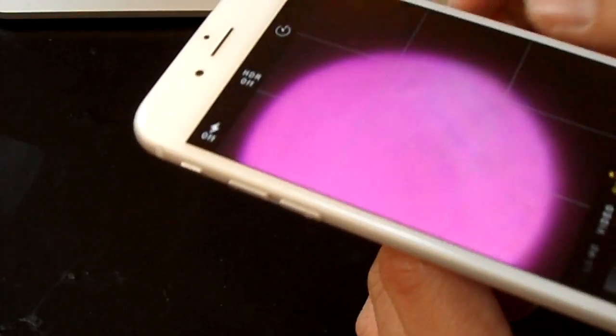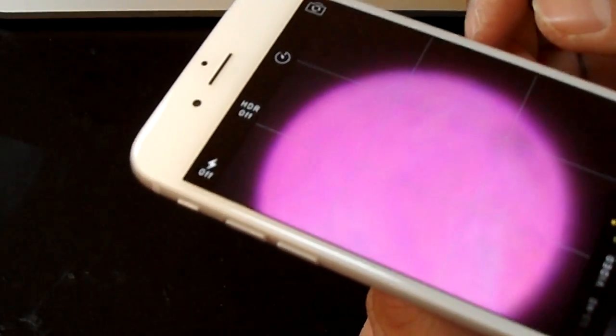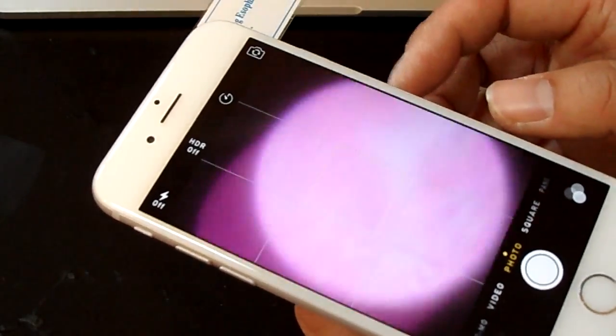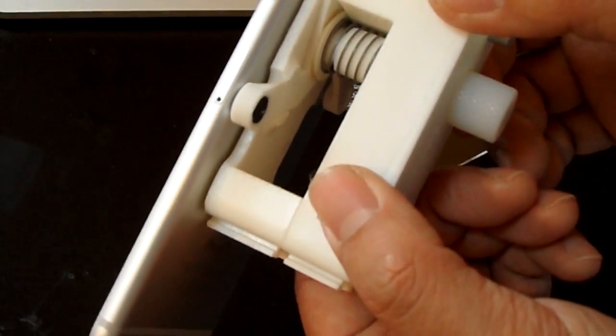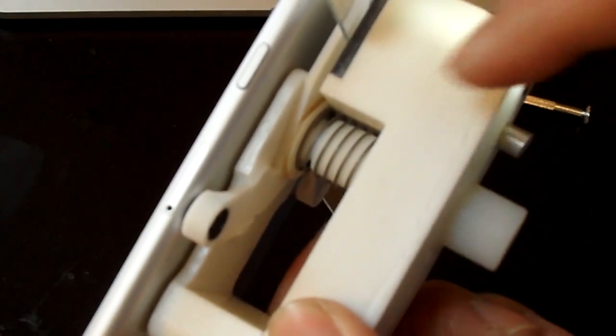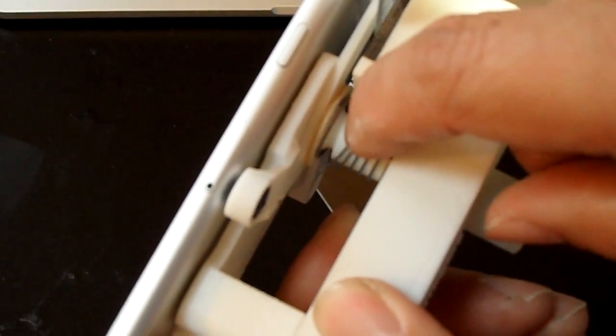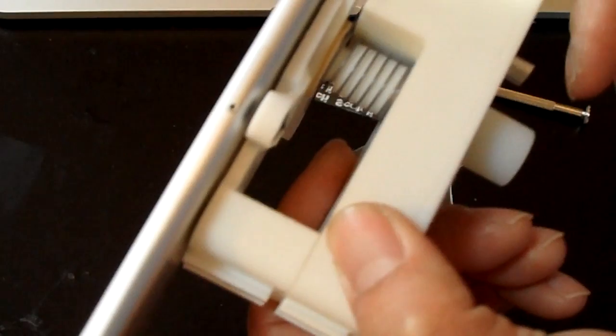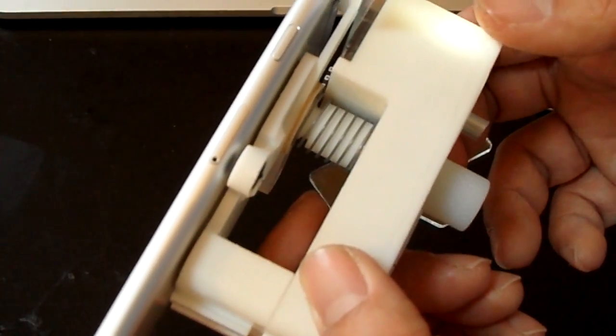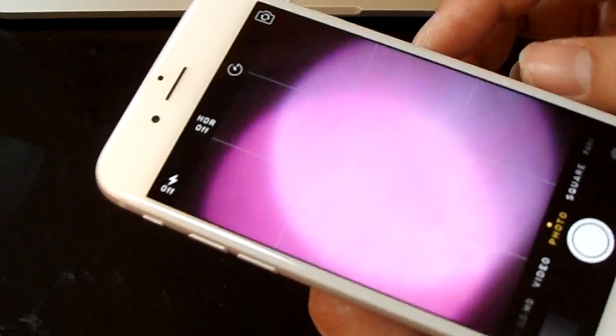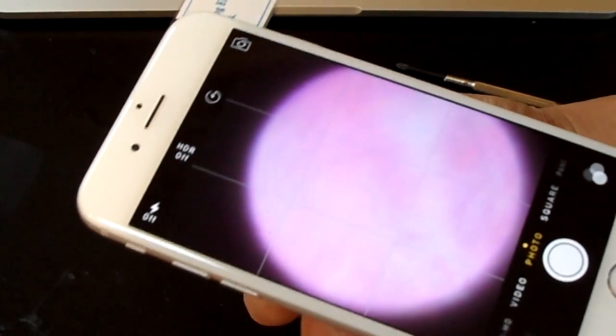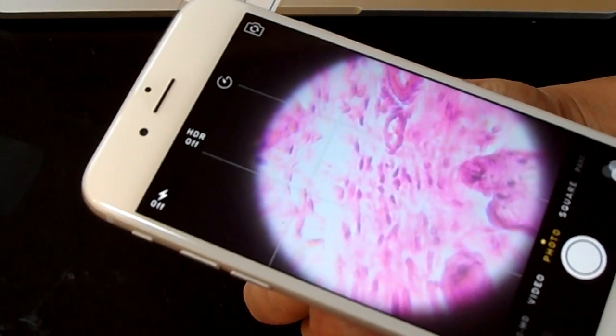And now I'm going to change it to the 340x lens. And as you can see here, there's a little issue. The microscope is not quite aligned, and that's because there's a little give in that detent right there that holds the lens in place. And the reason why it's like that is because the spring can fold in on itself and kind of move around a little bit. It's a kind of a weird problem that I discovered. But you can actually make use of that by setting that as the center when you first align the lens and the camera, and that'll keep the lens assembly always in the same position.